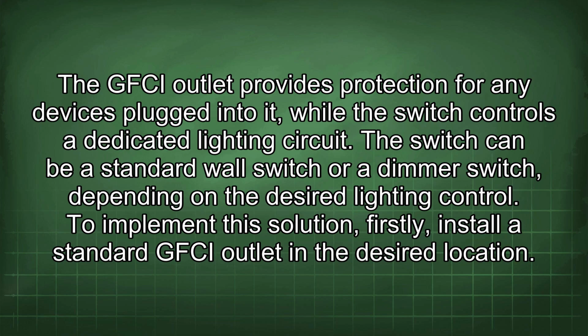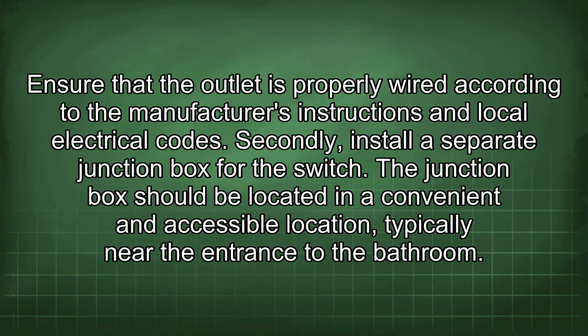To implement the solution, firstly, install a standard GFCI outlet in the desired location. Ensure that the outlet is properly wired according to the manufacturer's instructions and local electrical codes. Secondly, install a separate junction box for the switch. The junction box should be located in a convenient and accessible location, typically near the entrance to the bathroom.